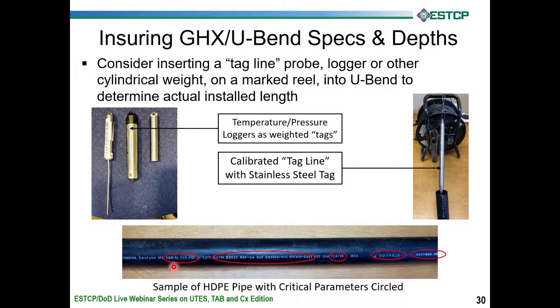And then the thickness of the pipe that you specified. The thicker the pipe, obviously the more robust it is, but the crappier the heat transfer is. Sometimes on really deep wells, you might go as thick as SDR, standard dimension ratio, of 9, which means the thickness of the pipe is roughly 1/9 of the diameter of the pipe. But SDR 11 is more appropriate, and occasionally you can get to thinner pipe, even like SDR 13.5. But SDR 11 typically is rated at 200 psi, and so you see that stamped on the side. So we think it's very important to look for those parameters when you're out in the field inspecting the pipe for commissioning purposes.